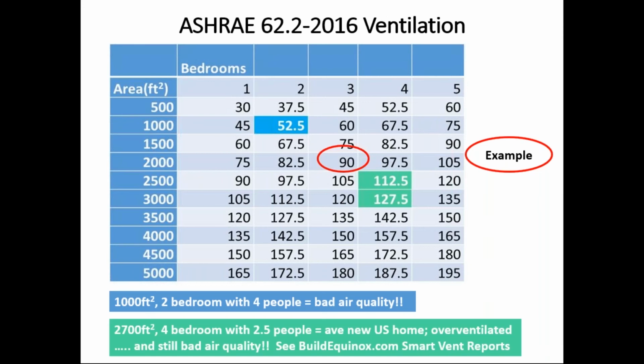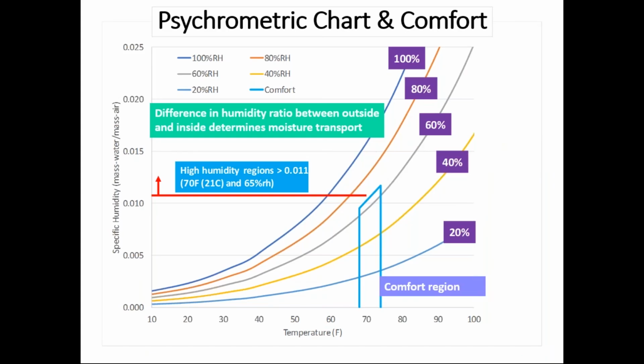So we're going to work an example for a 2,000 square foot, three bedroom home that would require 90 CFM of ASHRAE ventilation. A little bit about the psychrometric chart. Our friend Willis Carrier in 1911 came up with this and published a paper on the psychrometric chart, which is an extremely clever way of capturing the effects of humidity and temperature, or what we consider sensible conditioning. On the left-hand side is what's called specific humidity, or a similar parameter, humidity ratio, which we'll be using, basically the mass of water to the mass of the air, and relative humidity, which are the curved lines.